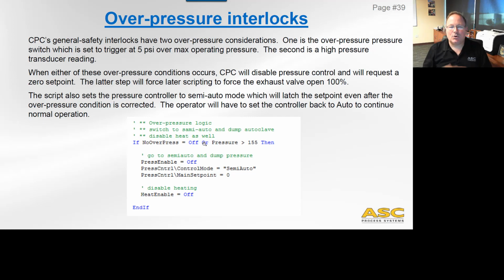Because we consider overpressure to be a much more important and dangerous thing, we're not just going to set valves or turn off pressure enable intermittently, and then when the overpressure switch registers that it's okay again, allow it to pressurize again. We're going to switch it to the semi-auto mode and put a main set point of zero. And what that's going to do is go to zero, and even after the no pressure switch condition has been reset, it's going to keep going down until the operator changes control mode back to auto or changes the main set point. So this is basically like a latch. It's going to latch the corrective action, and it's going to keep going to the bottom, okay?